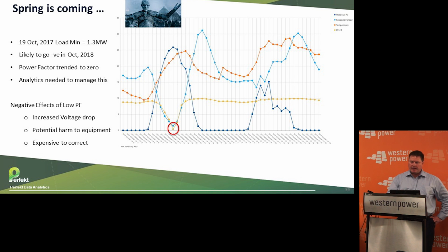So as we know, when you've got very low base load power on your zone substation and you're feeding in tons and tons of PV, you end up with major power factor degradation because the phase of the solar can differ, and you get huge VAR variations. Here, the power factor of the T1 circuit of Waikiki actually went to zero, and it did get reverse flows for 45 minutes. T2 didn't, that stayed positive, and T3 was missing. So I don't know, but there's a bit of that going on.